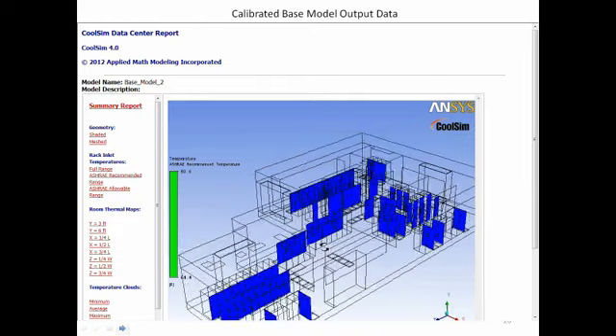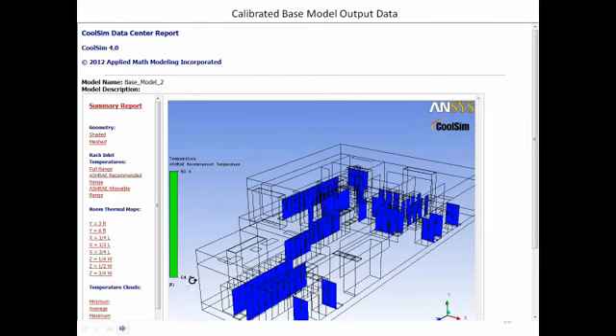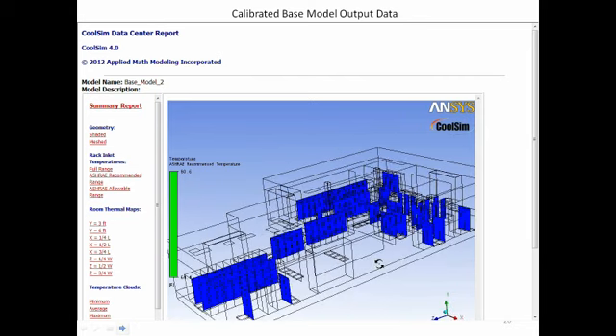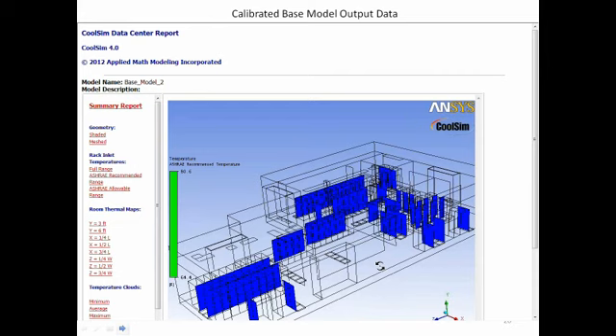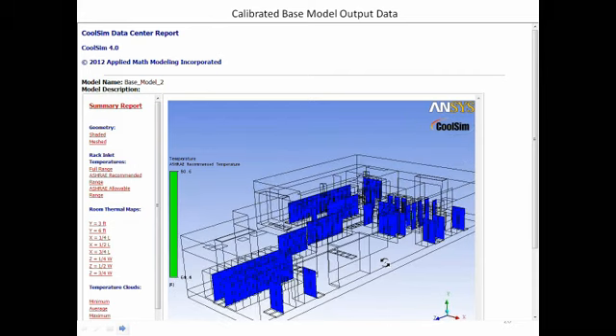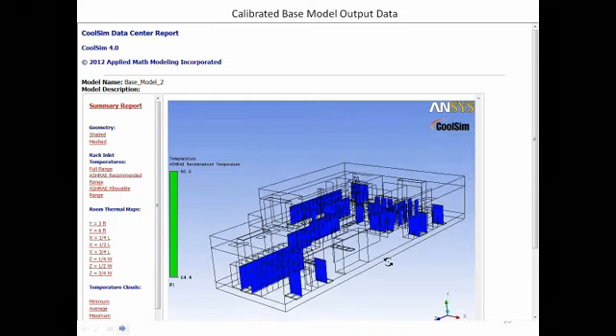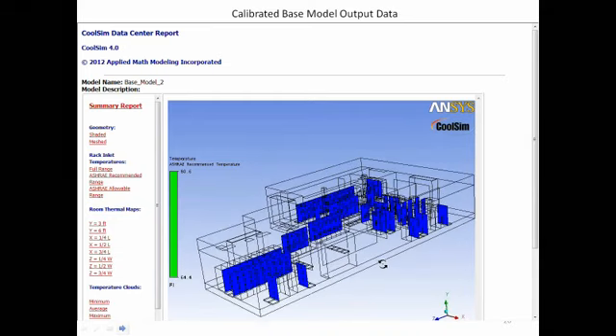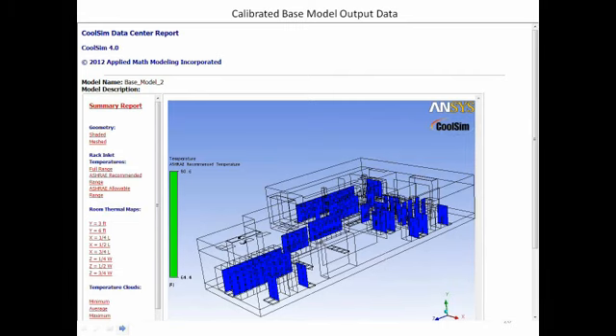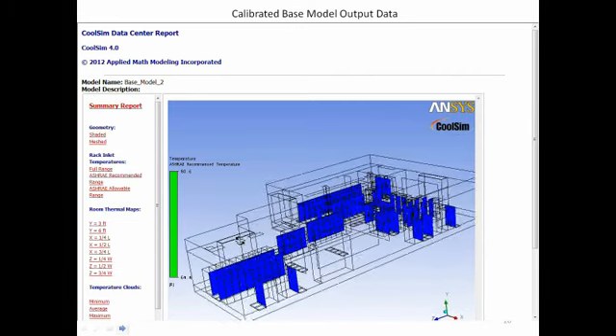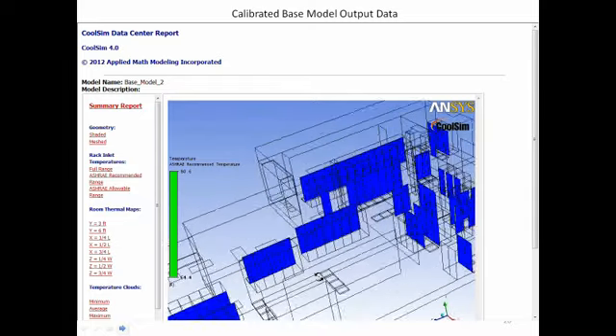So what we've done here, and Liz did this work, and it's very nice work, is we've said the range of acceptable behavior for these rack inlets is set by the Class I standard, 64 to 80. If you're in that range, your rack inlets will be green. If you're below it, they'll be blue. If you're above it, they'll be red. So we call this the Visine test, get the red out. But also the blue is too cold. So you can tell in one quick snapshot whether or not your servers are within spec. And you can see here they're not.